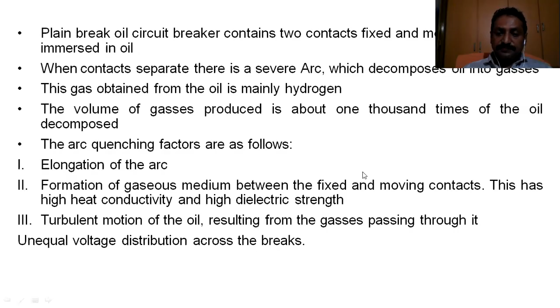That is about the plain oil circuit breakers. Next, the second categorization of the oil circuit breaker is the self-generated pressure oil circuit breaker. Very simple. In this self-generated pressure oil circuit breaker, arc energy is utilized to generate high pressure, meaning that whenever this oil is pumped between these two contacts, immediately that oil is converted into deionized gases. That gas is nothing but the high pressure established in the chamber.